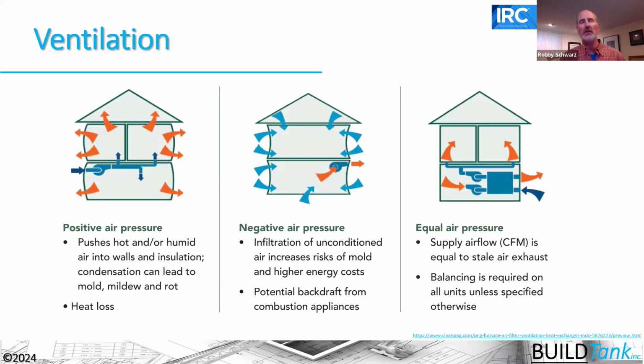So to gain the most control and predictability, I'm going to move to an equal pressure or a balanced pressure strategy with our ERVs or HRVs, where I know where the air is leaving the house. I know where the air is entering the house. I can do some type of exchange across that coil, so I can keep some of the heat in the house in the winter season. I can potentially keep moisture in the house as well, because we tend to have more moisture inside our houses than outside our houses in climate zones 6, 7, and 8, and even in climate zone 5, and well, in Colorado in general, we do. So I might want to control that moisture flow as well, using an ERV over an HRV in our climate zones.